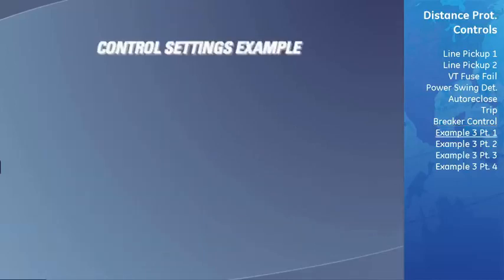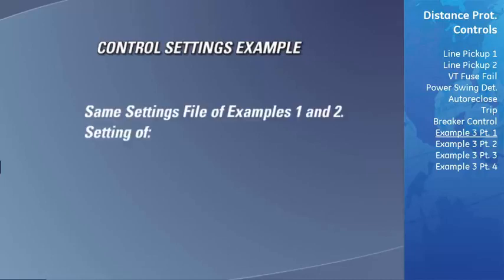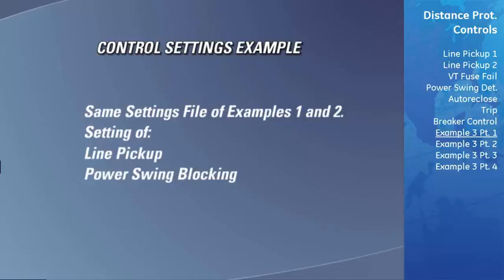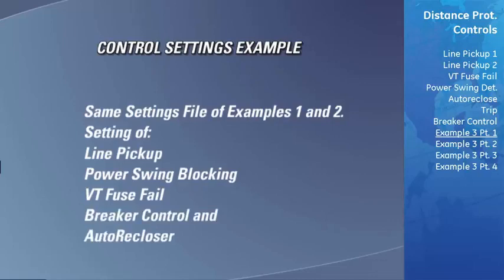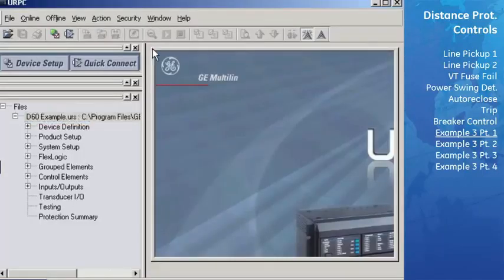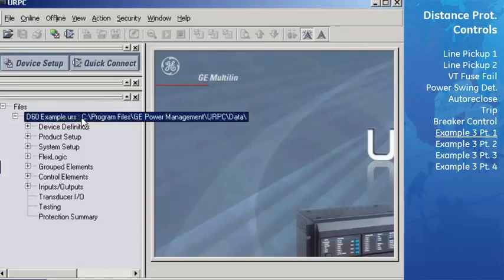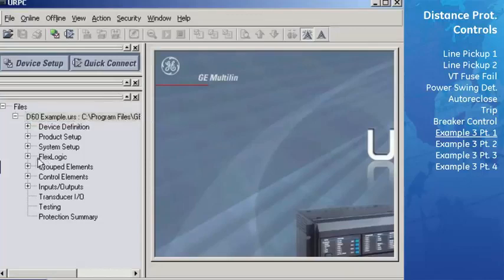In the few final sections of this learning CD, we will give an example of how to set up and configure all of the control and protection elements we have just described, including the line pickup element, the power swing blocking element, the VT fuse fail function, the breaker control element, and the auto recloser. Finally, we will assign the outputs of these functions to the contact outputs to complete all of the settings necessary for our D60 transmission application.